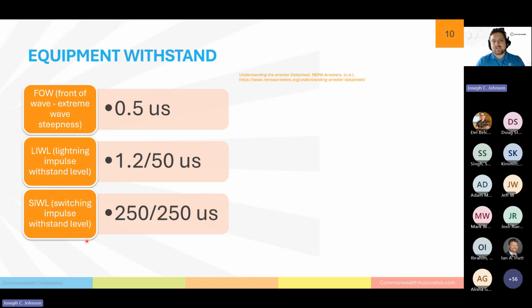So that basically is a test to see how individual portions, and the weakest portion, of insulation can actually withstand, because this wave is rising so fast that the voltage doesn't actually have time to balance across the insulation. It kind of gets stressed at a single point of insulation. That's about how you're going to see your biggest point of failure for individual points of insulation along your conductor or insulator stack. The next is the lightning impulse withstand level. That is to simulate a lightning strike, and that is a 1.2 microsecond rise time. It's a little bit slower, but still crazy fast.